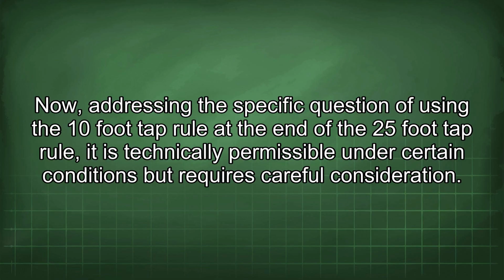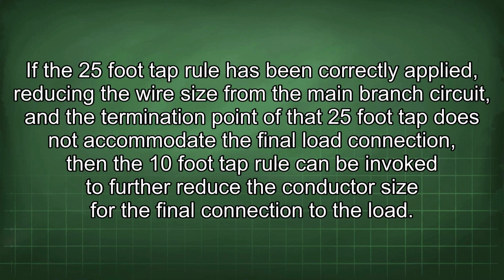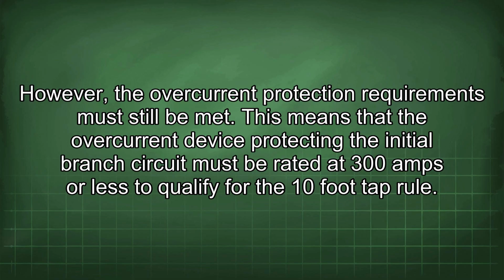Now, addressing the specific question of using the 10-foot tap rule at the end of the 25-foot tap rule, it is technically permissible under certain conditions but requires careful consideration. If the 25-foot tap rule has been correctly applied, reducing the wire size from the main branch circuit, and the termination point of the 25-foot tap does not accommodate the final load connection, then the 10-foot tap rule can be invoked to further reduce the conductor size for the final connection to the load. However, the overcurrent protection requirements must still be met. This means that the overcurrent device protecting the initial branch circuit must be rated at 300 amps or less to qualify for the 10-foot tap rule.